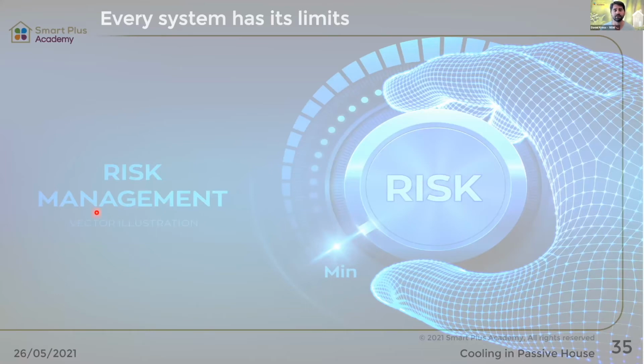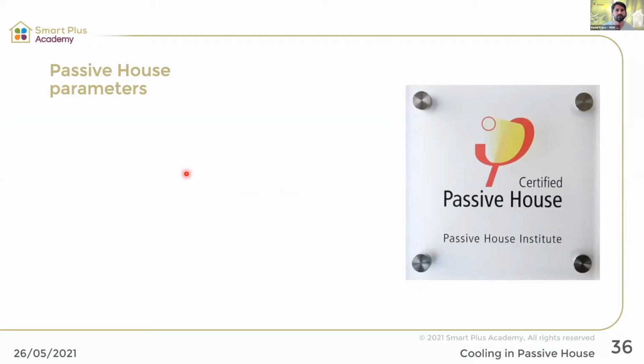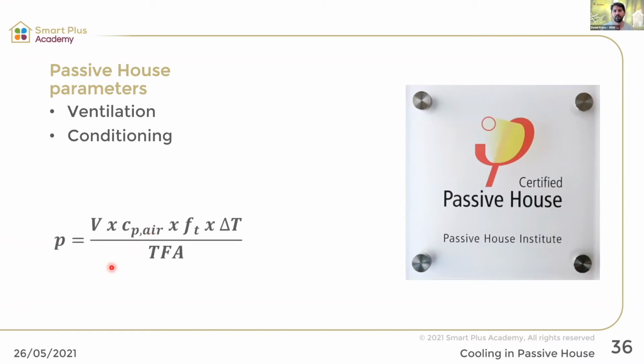So to understand our systems, we need to understand the parameters and the risk parameters. The passive house parameters we need for heating and cooling are ventilation, conditioning, and the capacity of our cooling, given by this formula, which creates our maximum load, the size of our system. V is the volume of air available as our medium for cooling. CP is the capacity of air, the thermal mass of air. FT is just a correction factor. Delta T is the thermal difference in your location related to your treated floor area, that's the conditioned space. That's the formula for the maximum load we can deliver to our passive house.